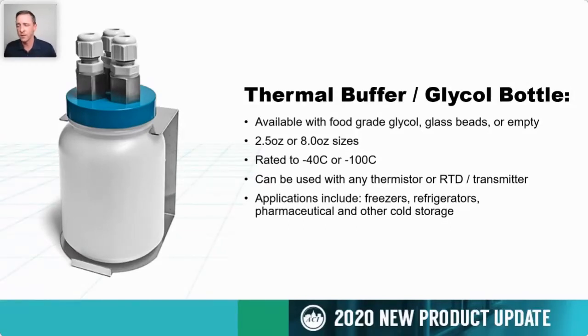And they can be paired and used with any thermistor or RTD sensor, or RTD paired with analog transmitter. And these are for applications for cold storage or very low temperatures, freezers, refrigerators, pharmaceutical storage, and any other type of cryogenic application. The idea here is that these provide a buffer so that if a cooler or freezer door is opened, the sensor doesn't get hit with a rush of room temperature air and put the system into an alarm status. So it essentially slows the response time down so that you can get a better trend of what the temperature is in that space.